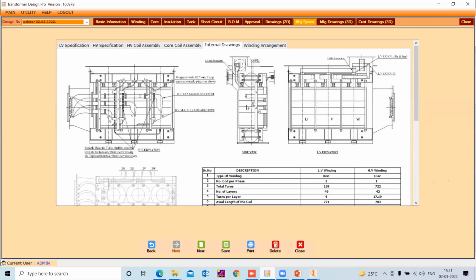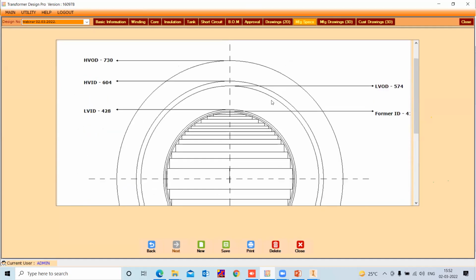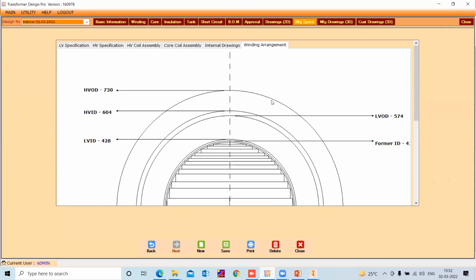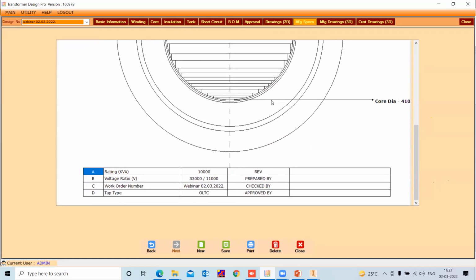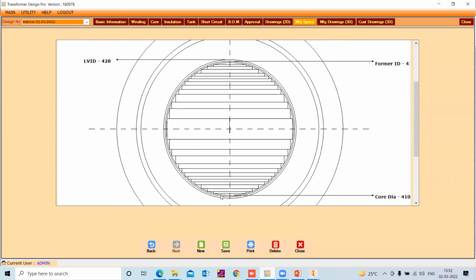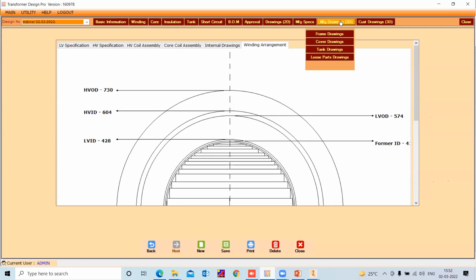This is the internal diagram for OLTC. Now you can see the leads for OLTC are outside. Here you can see the size as compared to 1500 kVA. This is automatically changed. And this number of steps you will get exactly what you have selected or what the software has in step stack calculation. Now next are the 3D diagram for the same. Let's open the frame diagram. And this 3D diagram you can also export to AutoCAD, and there also you can do changes if you wish, or if you are familiar with AutoCAD.